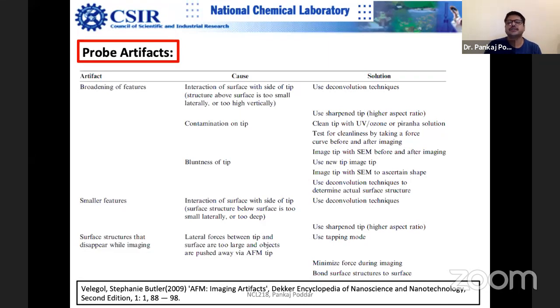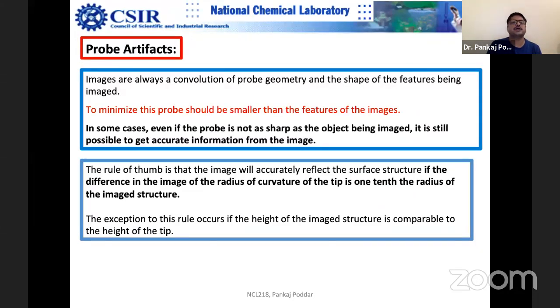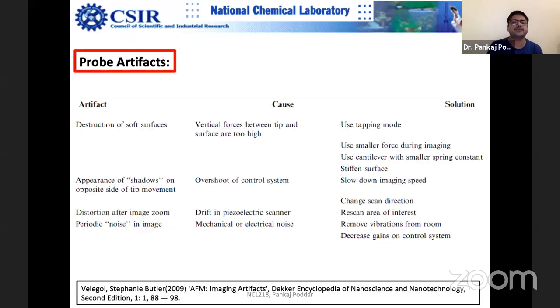Deconvolution technique is sometimes quite hard because you need information about the tip radius of curvature; otherwise it is difficult to deconvolve. Artifacts due to probes can be subdivided into three parts: size of the tip relative to the sample, tip-sample angle, and sidewall interaction. Probe-sample angle is quite important — if you have a pit with 90-degree sidewalls, making sure you are actually measuring the bottom of that pit is a tricky question.